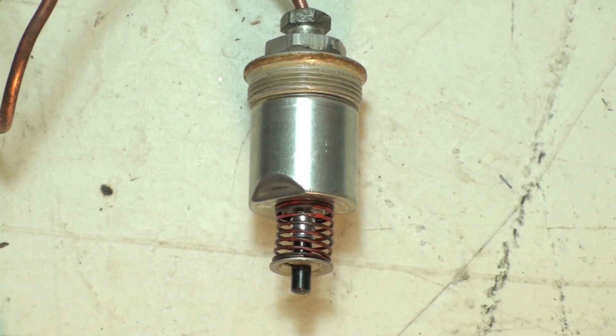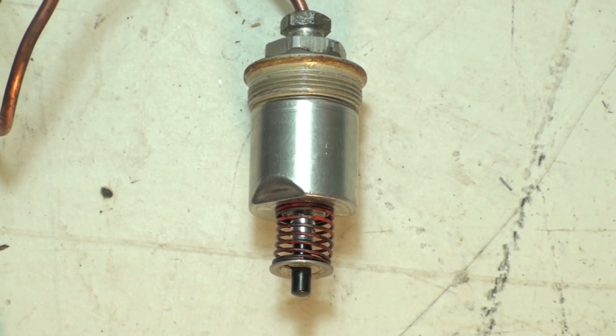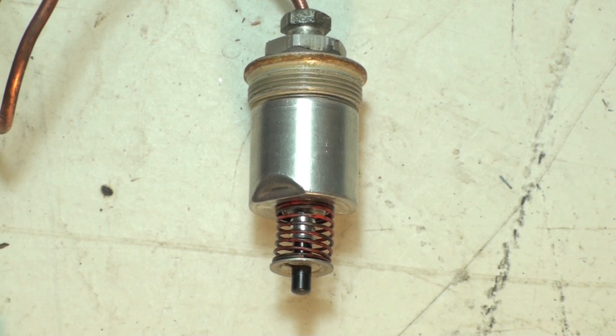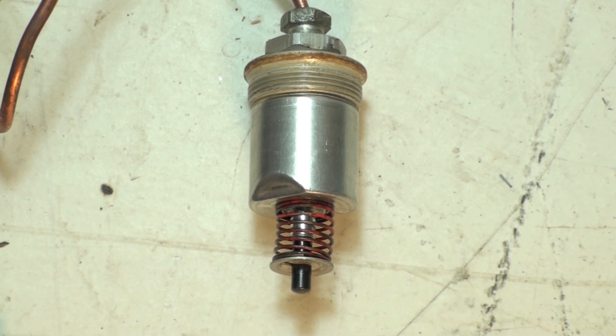Okay, there you can see it has dropped out. It took about a minute and a half. And that's a normal thermocouple. The solenoid's working okay.